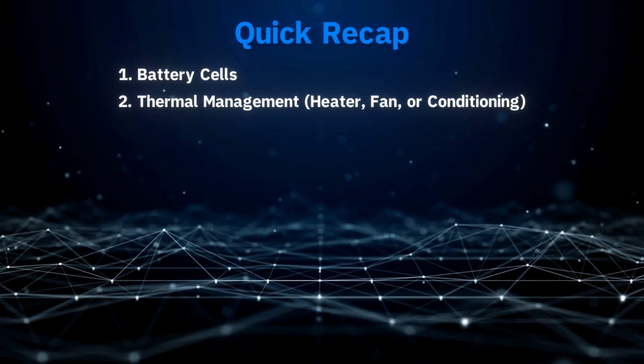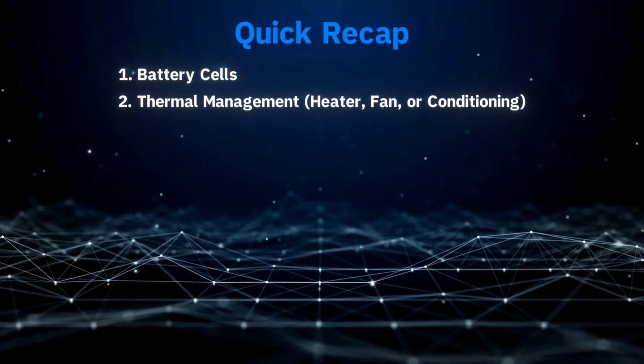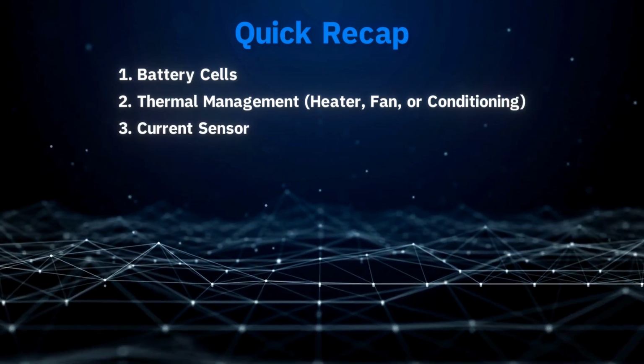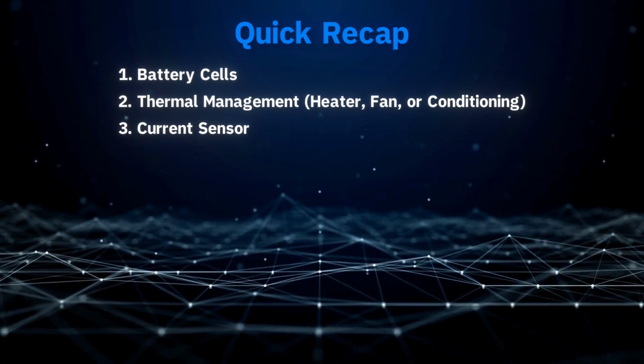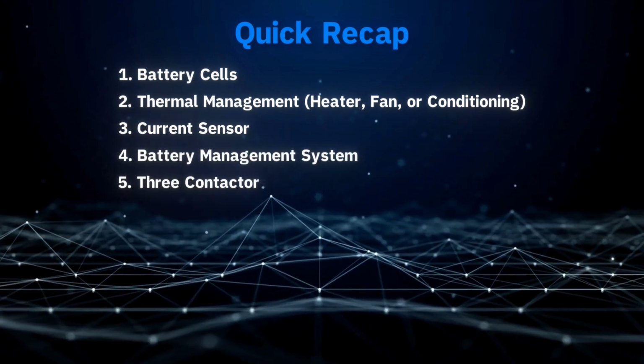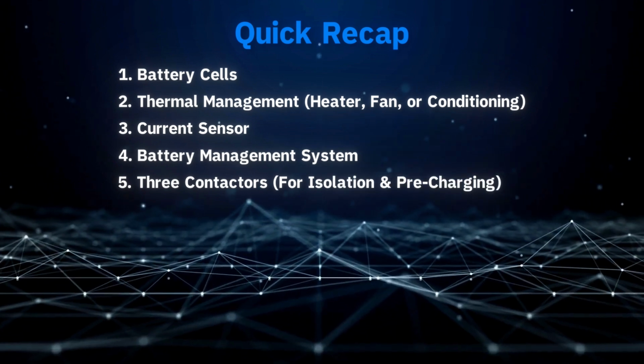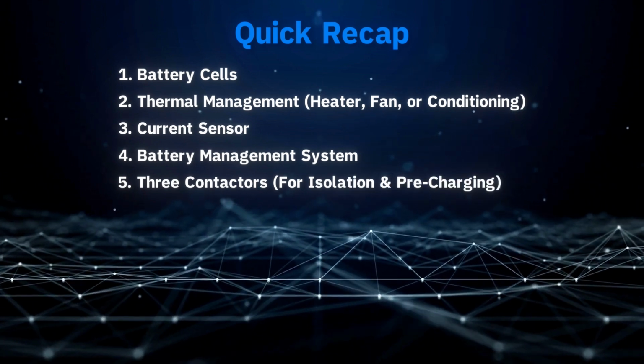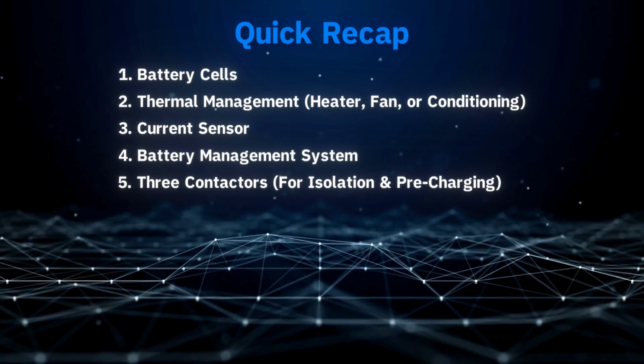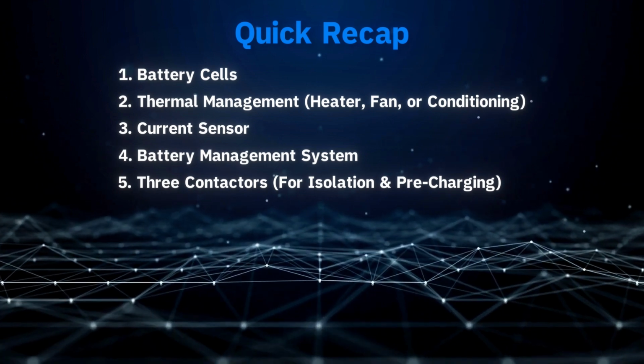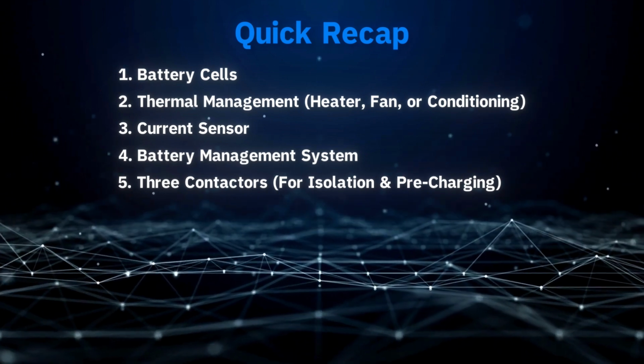Quickly, to recap: number 1, you're going to find some sort of thermal management—a heater, fan, or air conditioning. Number 2... number 3, you're going to find a current sensor. This current sensor reports into number 4, the battery management system. Number 5, you're going to find 3 contactors, which enable the battery system to isolate the high voltage and enable precharging—opening the tap slowly before opening the floodgates.